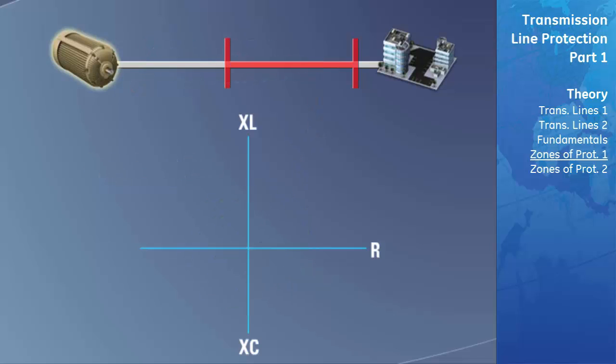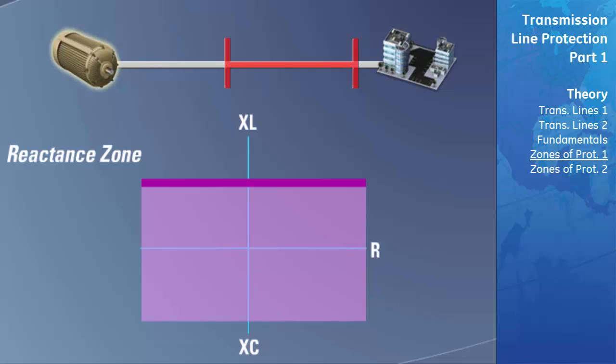The zone of protection shown here is known as a reactance zone. This type of zone is used to detect when the impedance of the fault has a very high resistive component in it. If the fault does have a high resistive impedance, this indicates that there is a load on the transmission line and the fault is most likely not on the transmission line. This type of zone is usually never used to trip a transmission line on its own but is normally used to supervise another distance zone of protection.